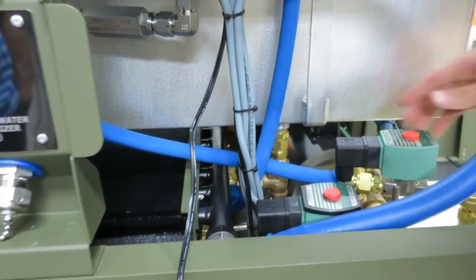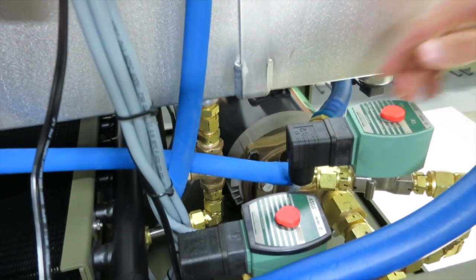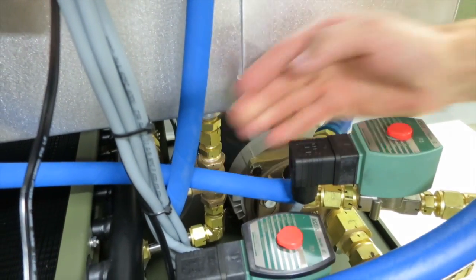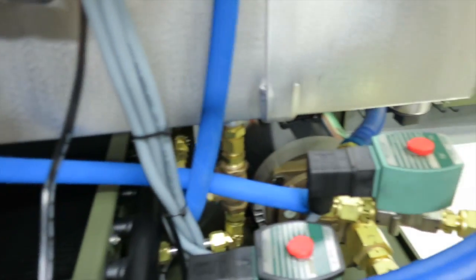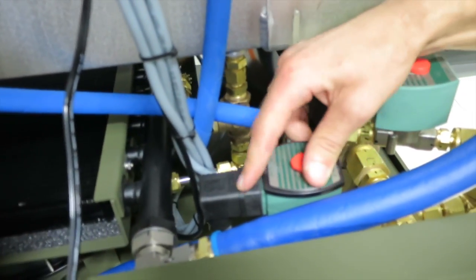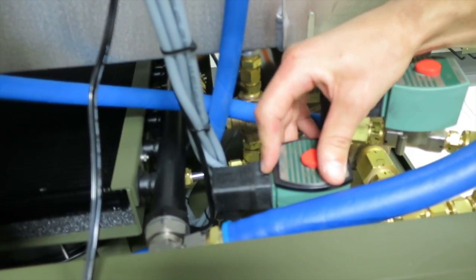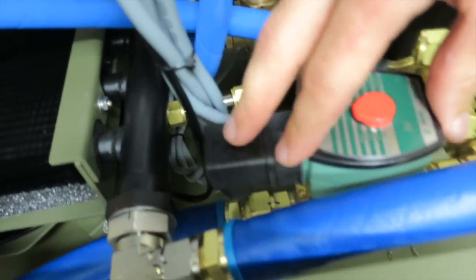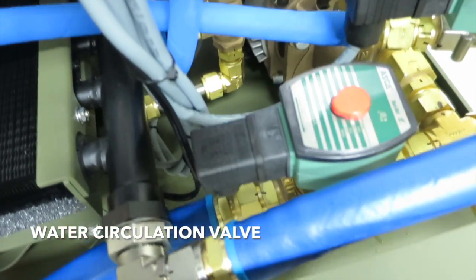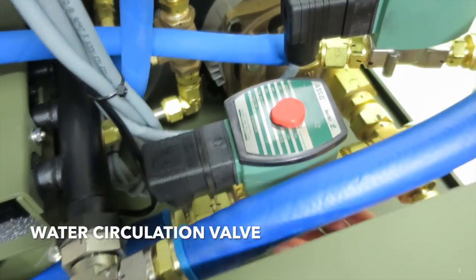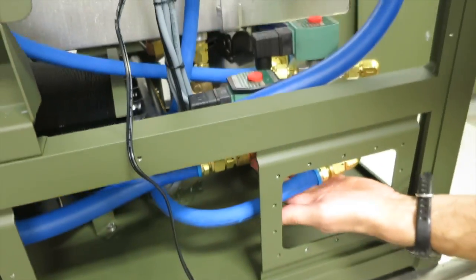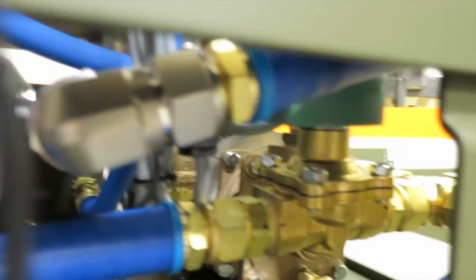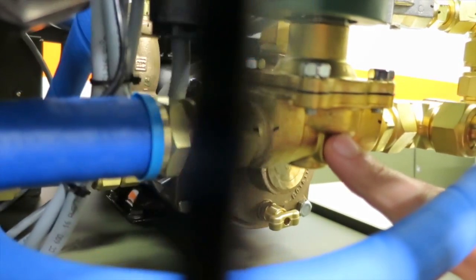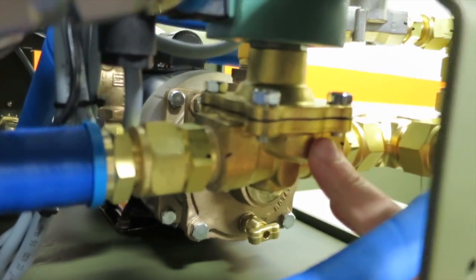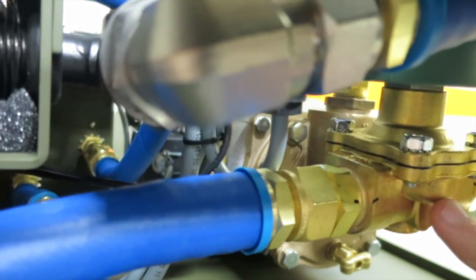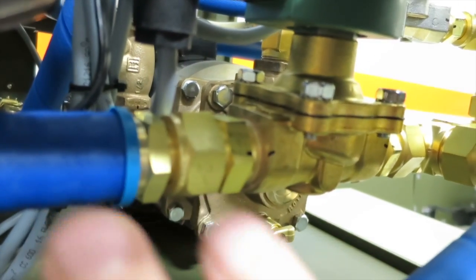So again, anytime you press that toggle switch, it activates a relay, opens up this valve, and allows you to pump water to the sterilizer. Also, when you activate that toggle switch, you are closing the water circulation valve. This valve right here is a different design, it's a bellows valve, and it is normally open. So when it's de-energized, it's open, which allows water to flow through it and circulate.